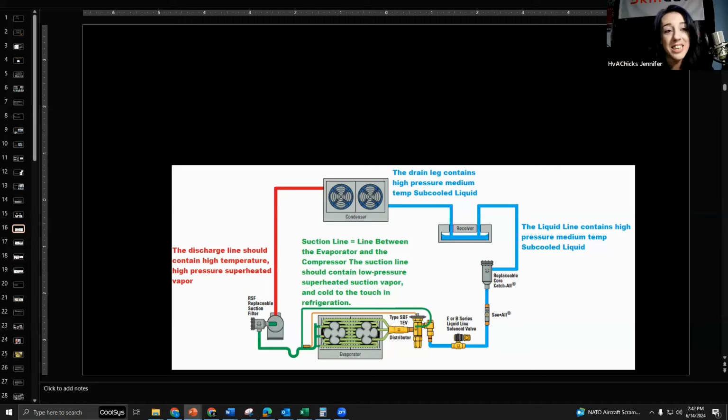That's another thing we can do in a non-invasive system check, you guys. So, I did a video talking about non-invasive checks. Remember how I was saying, in your 75 degrees, 20-degree TD on top of that, which brings you up to 95. And then usually you get about 5 degrees of subcooling. So if your liquid line would theoretically be 90 degrees, then that's your non-invasive check.